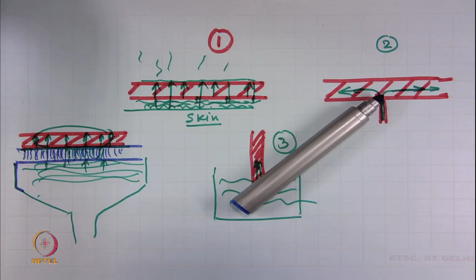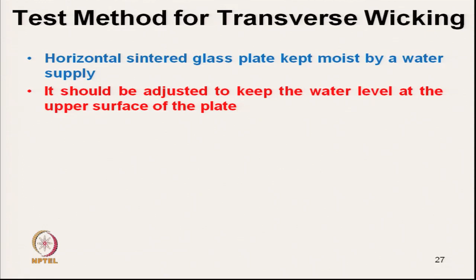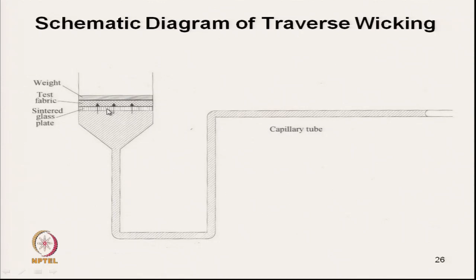So, in this instrument there is a capillary tube, which may sometimes be a flexible tube, and here it is the water supply. The horizontal sintered glass plate is kept moist by the water supply. Always we have to keep supplying water from the bottom. It should be adjusted to keep the water level at the upper surface of the plate, so that the top surface of the plate is always moist.